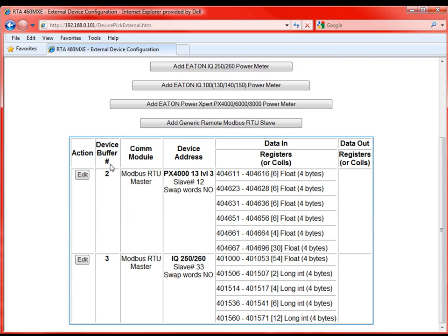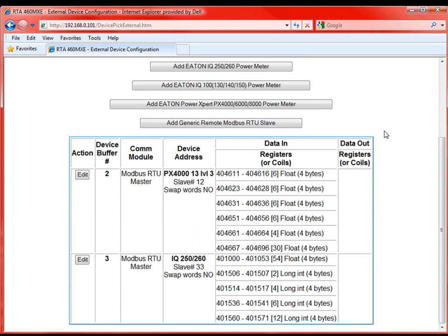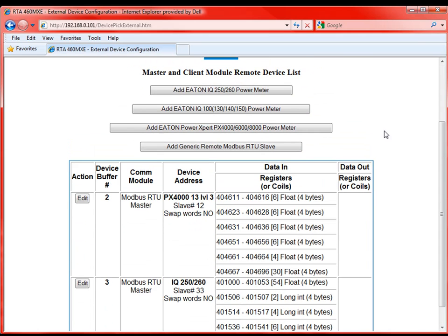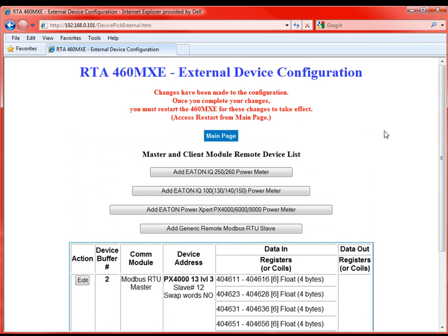Here we are able to add connection to up to 31 devices. What I will say is that if you add all 31 and you're looking for very fast polling, poll times, it may be a good idea to get another gateway and limit that. The more devices we have to scan obviously it adds a little bit to latency. The good thing is though generally in building automation applications there's not a need for super fast data. These rates aren't something you have to monitor on the millisecond level. It's not generally like process type data. So slower polling is generally acceptable in building automation. And if that is the case we can certainly support up to 31 devices.